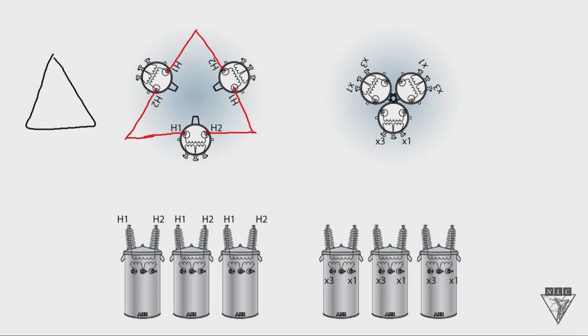So if we move down to the bottom and just do our transformer connections, we're going to tie our H1s to our H2s all the way around and then run jumpers up like they're each going to a phase. Let's go ahead and label these. We would have A phase right here, B phase, and C phase.